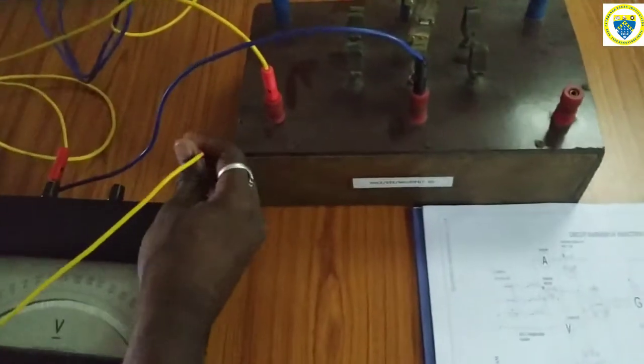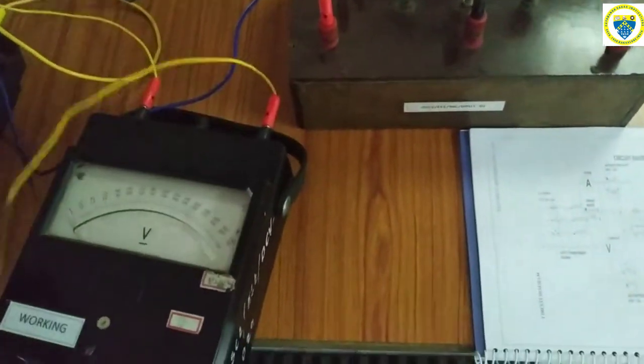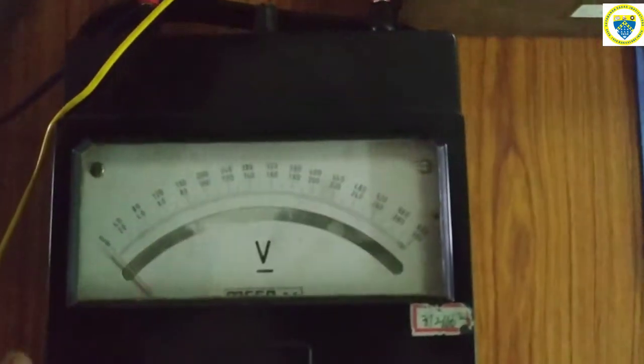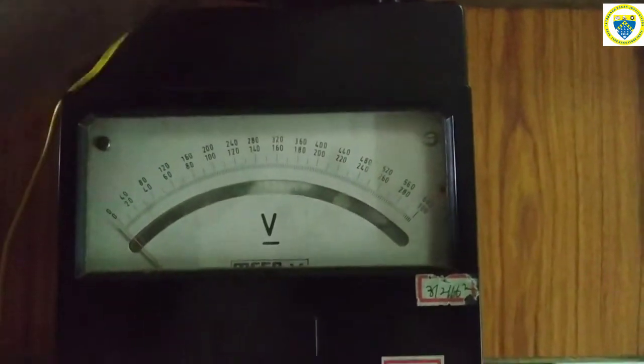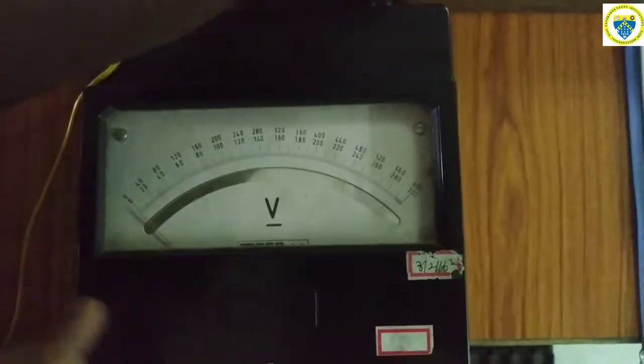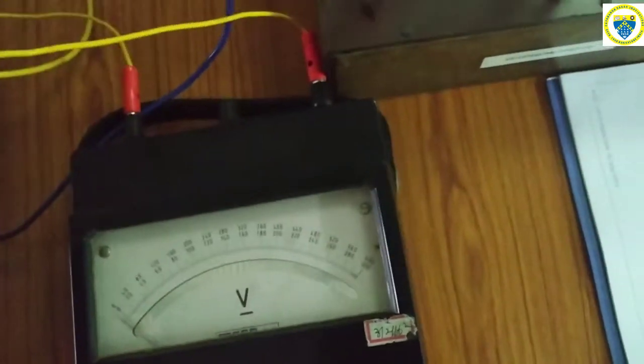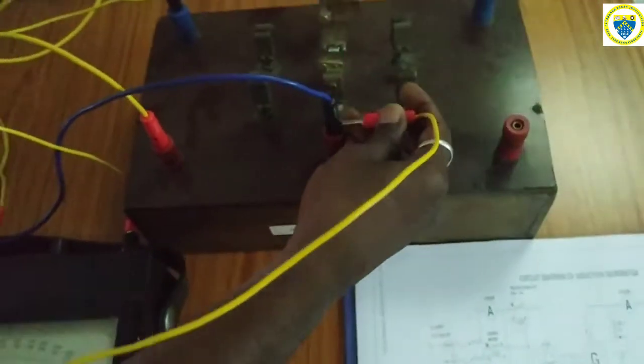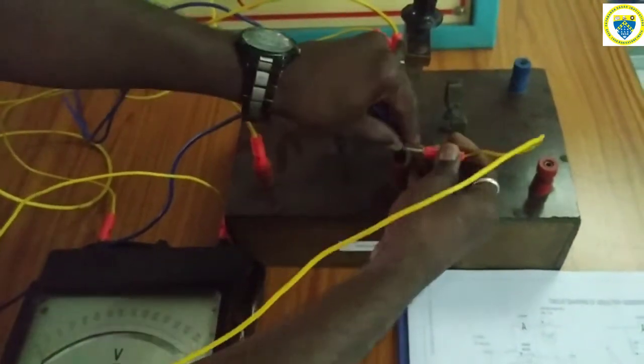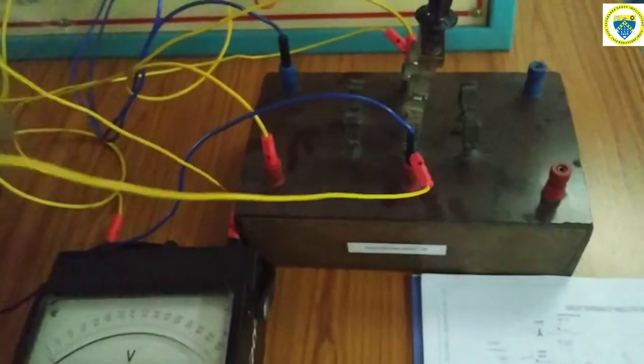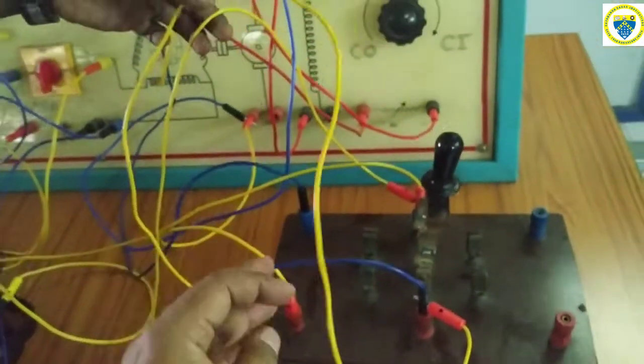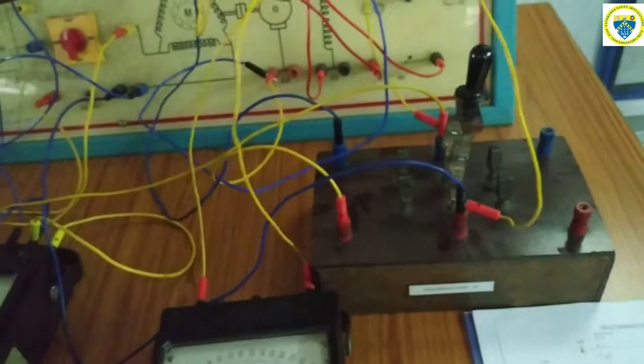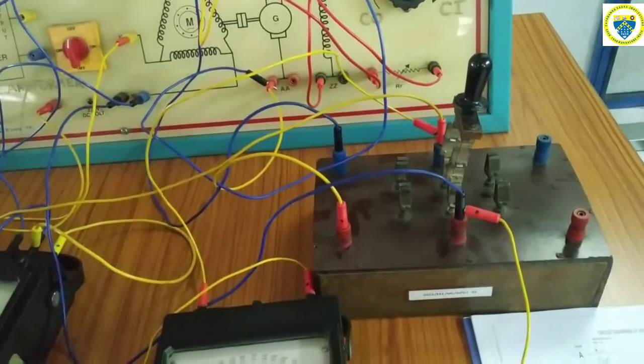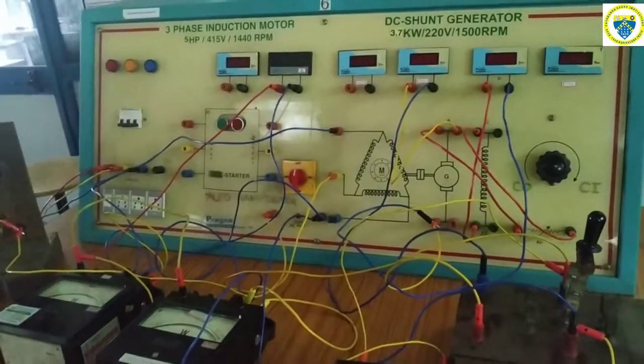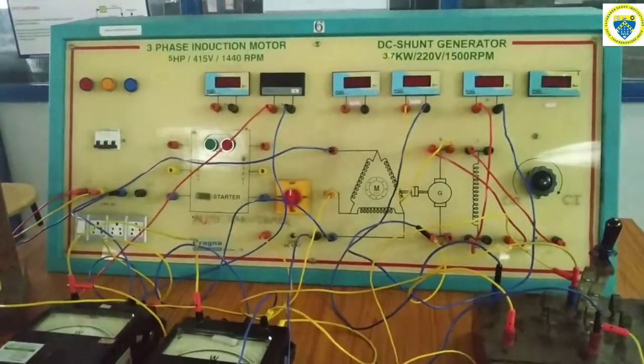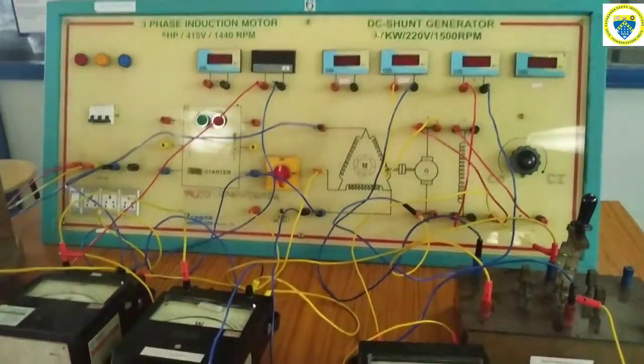Also, to have a reading for the DC voltage generated by the DC generator, we require this DC voltmeter, and it should be connected across the switch. So positive and negative terminals are connected here. This is the overall setup we have to conduct a load test on a DC generator.